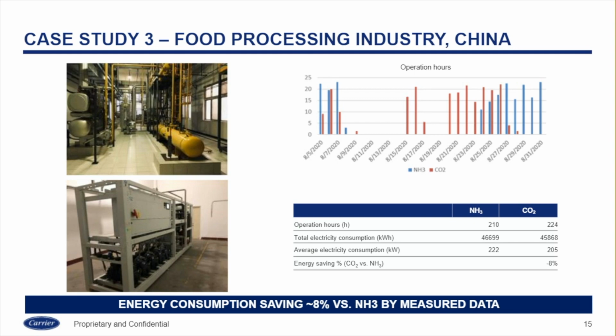We counted the operating hours, and we have the power to account for the total electricity consumption. Based on the data we collected from the field, the total energy saving for the CO2 system is about 8% compared with the ammonia system. Please bear in mind, this system has no ejector. If we have the ejector equipped in the CO2 system, then definitely we can get more energy saving compared to the ammonia system. As I just mentioned, the ejector can uplift the energy saving by about 17%.